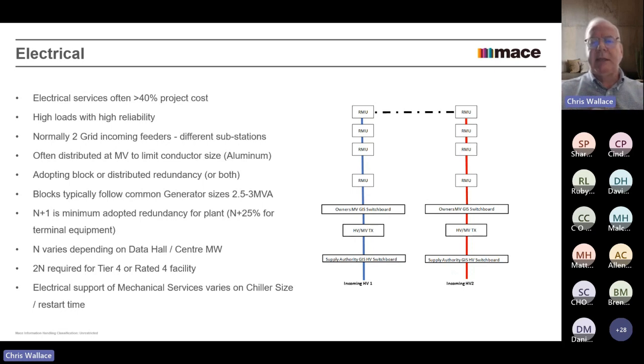So this will give you basically, if you look at it as the red and blue, an N plus one, and the N will depend on how many of these ring main units or how many blocks you need to feed your load. What I've just said in brackets there is that N plus one is really only for major plant. For terminal equipment, you may have N plus 25%. So if you're talking about cooling units, you would not go for N plus one because the units would be too big to actually work as a unit, something like that.